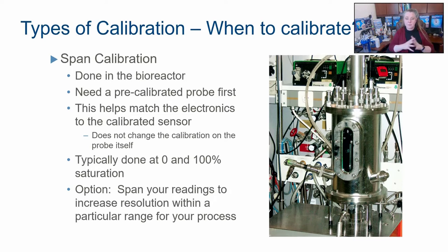That's totally acceptable. An even better way of doing it, which means you don't have to have a different recipe for every kind of media, is to have your oxygen probe in there reading. You're not going to calibrate yet. You're just going to read the output. And you're going to sparge with nitrogen. And you're going to have your impellers going with your media.